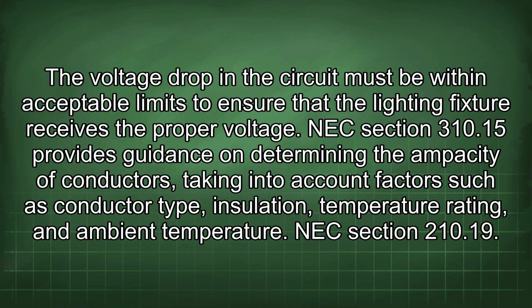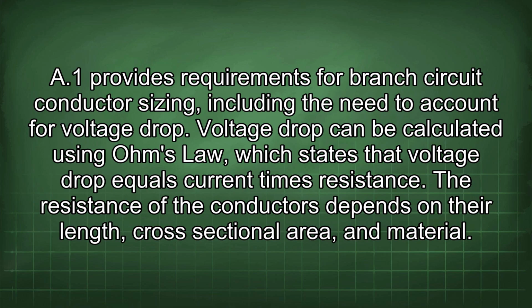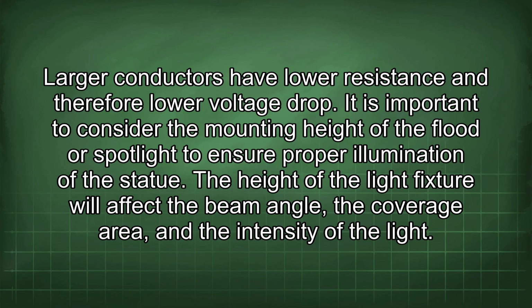NEC Section 210.19(A)(1) provides requirements for branch circuit conductor sizing, including the need to account for voltage drop. Voltage drop can be calculated using Ohm's law, which states that voltage drop equals current times resistance. The resistance of the conductors depends on their length, cross-sectional area, and material. Larger conductors have lower resistance and therefore lower voltage drop.